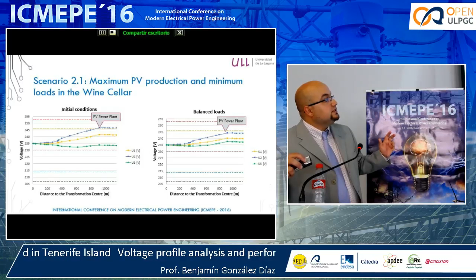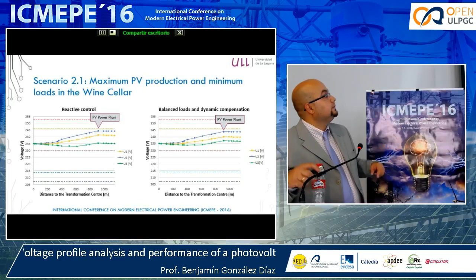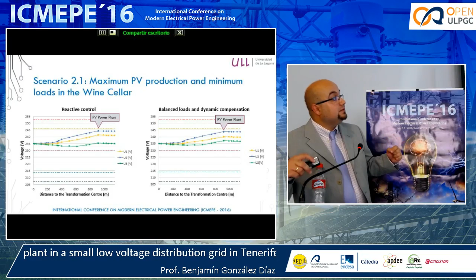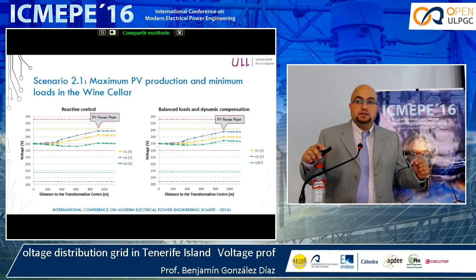If we balance the loads of the wine cellar, they are more or less at the limit, but this one is still so high. Using the strategy of reactive control, static reactive control through the capacitor bank they have, they are still at the limit, but there isn't a huge difference between them. Balancing the load and dynamic compensation reduces this difference a little, but they are still more or less at the limit.